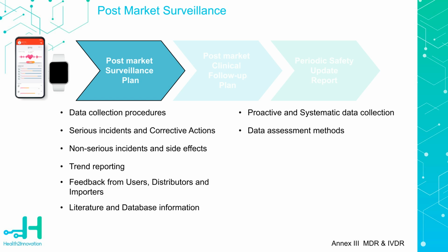It's important to have effective methods in place to assess data within the QMS. This supports data assessment and risk management activities. Use suitable indicators and thresholds to continuously reassess benefit-risk analysis. For example, if we set thresholds for acceptable false alert rates and take action if these are exceeded.